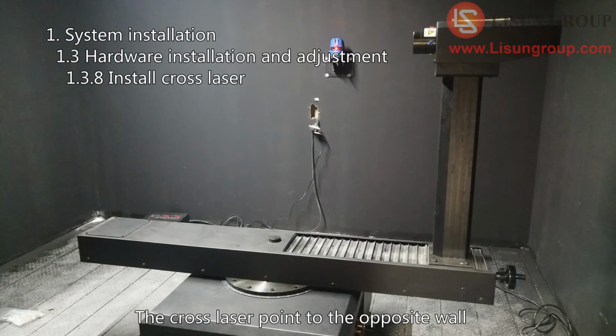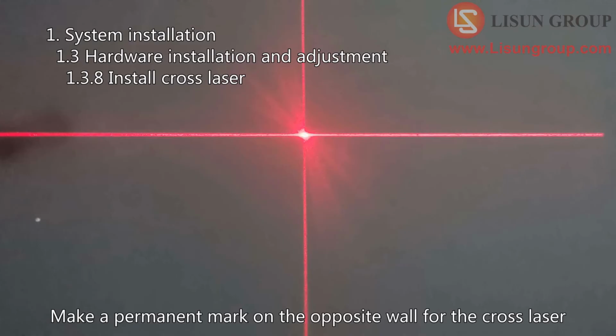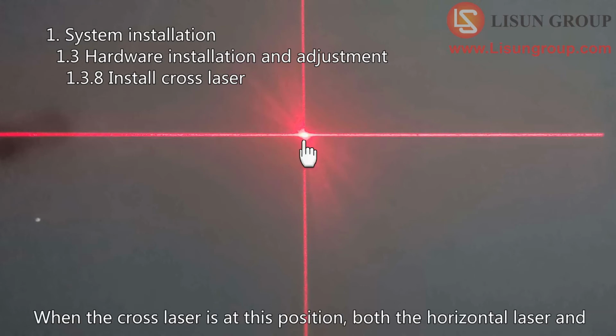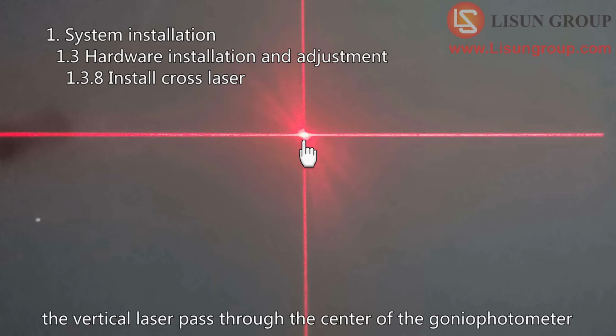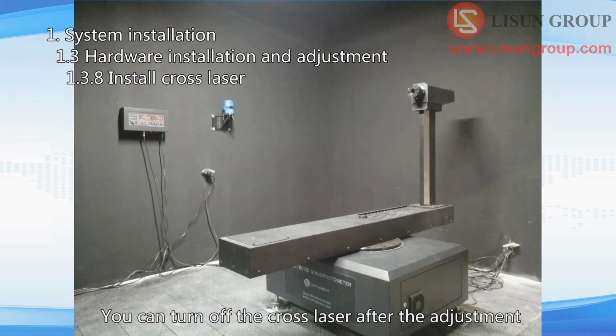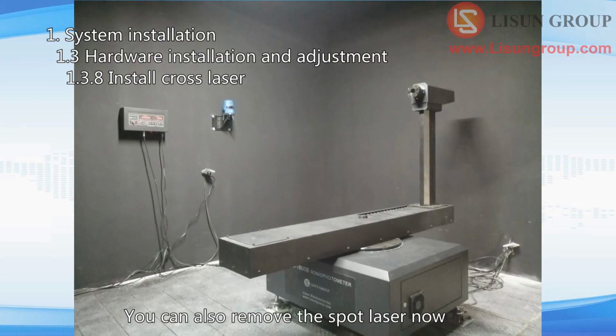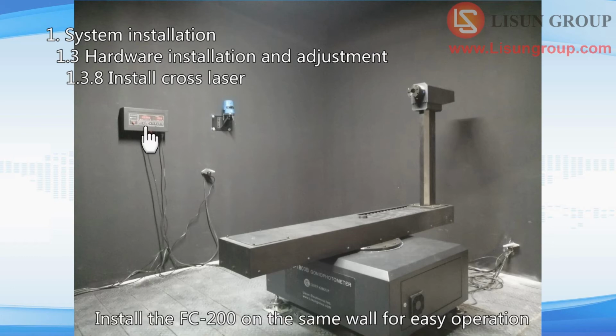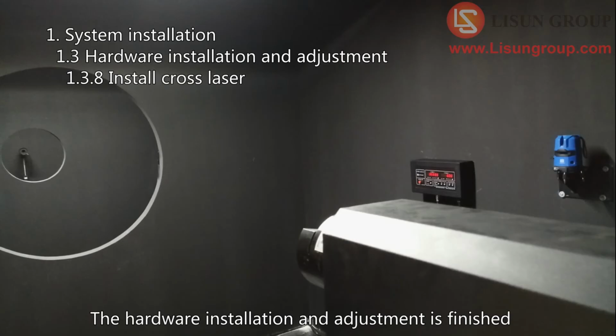The cross laser points to the opposite wall. Make a permanent mark on the opposite wall for the cross laser. When the cross laser is at this position, both the horizontal laser and the vertical laser pass through the center of the goniophotometer. You can turn off the cross laser after the adjustment. You can also remove the spot laser now. Install the FC-200 on the same wall for easy operation. The hardware installation and adjustment is finished.